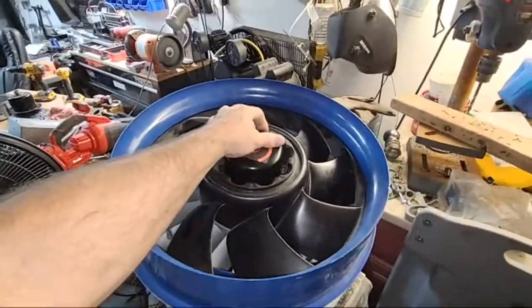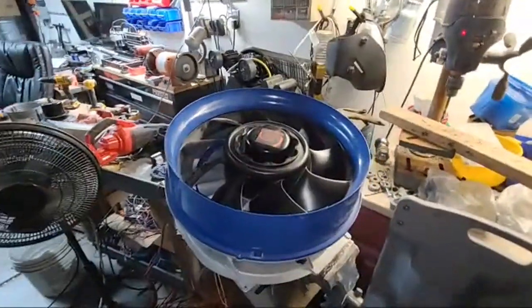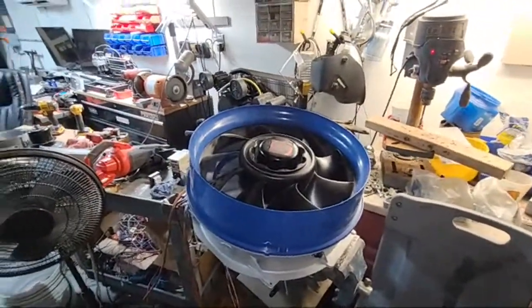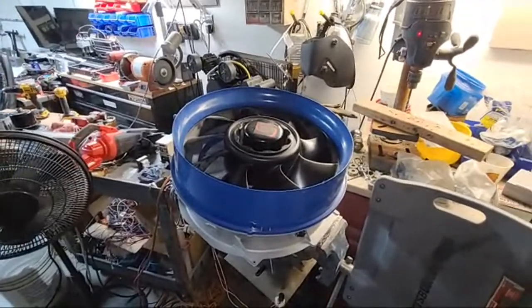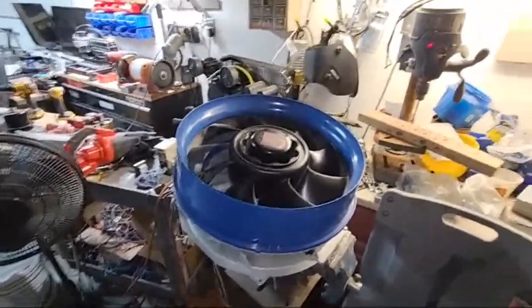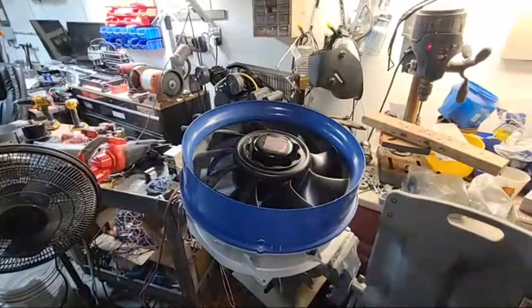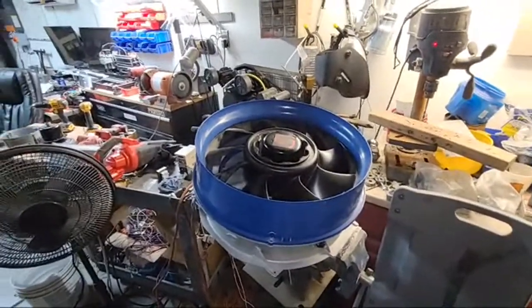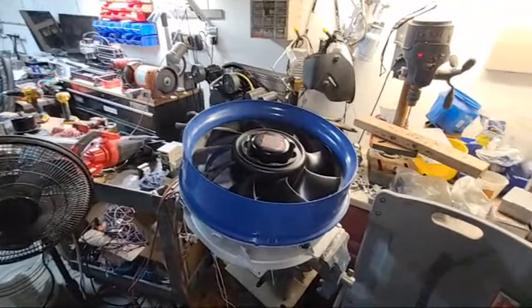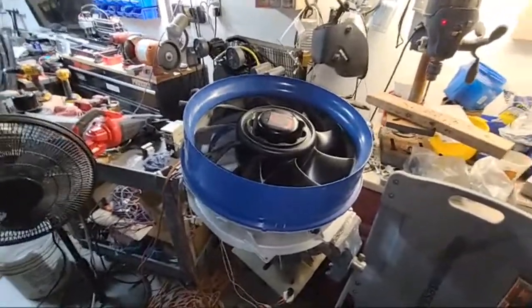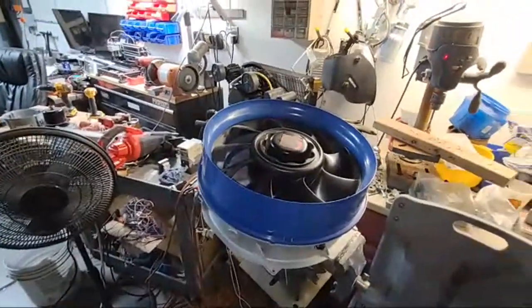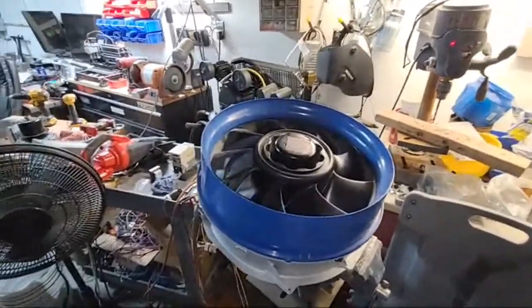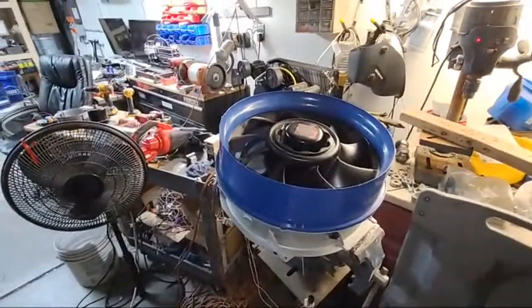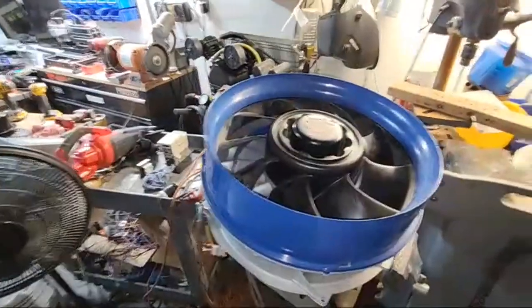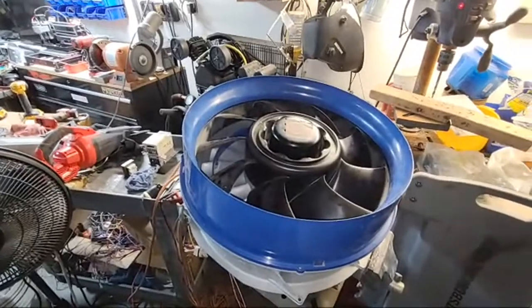But that's what they did, and they called it like a heater or something. I asked, and somebody chimed in on YouTube and told me, yeah, that's exactly what that is. It opens the expansion valve if the pressure gets too high, because it knows there's too much refrigerant stacking up in the microchannel, so it opens the needle and lets more flow into the evaporator, dropping the head pressure from the refrigerant stacking in the outdoor coil. Pretty funny what engineers come up with.